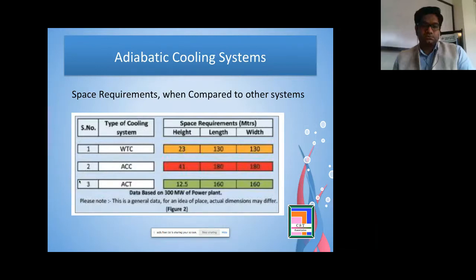So there is a comparison sheet between the WTC, which is the wet type cooling tower, ACC, which is the air cooled condenser, and ACT, which is the adiabatic cooling tower. So for a 300 megawatt comparison, our height requirement is 23 meters for WTC. WTC length is about 130 meters, and width is about 130 meters. Then for ACC, we require 41 meters as height, and length 180 meters, width 180 meters. And for ACT, which is the adiabatic cooling tower, we only require 12.5 meters as height, and length is 160 and width is 160 meters.